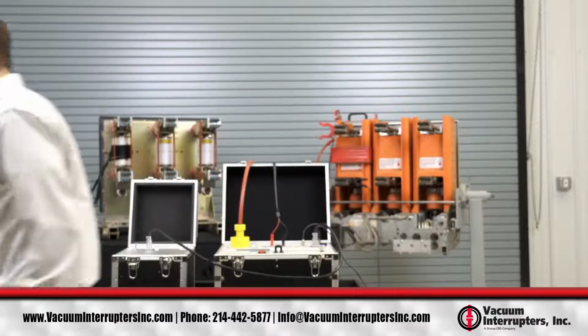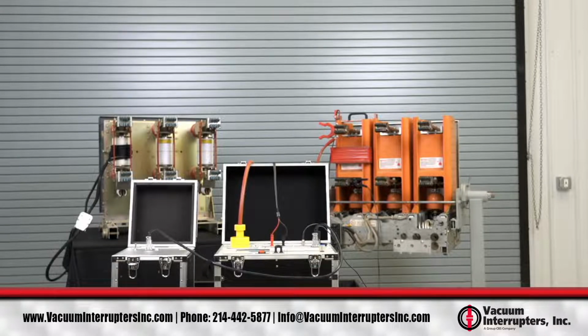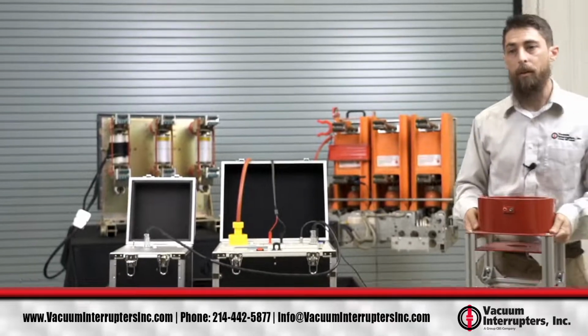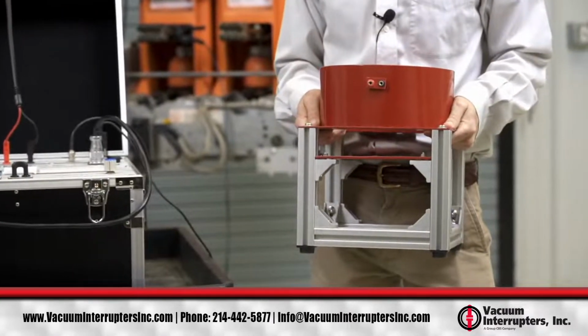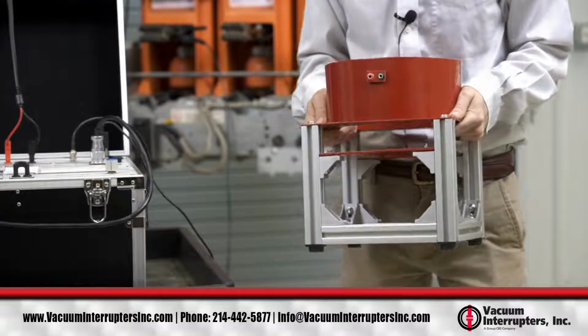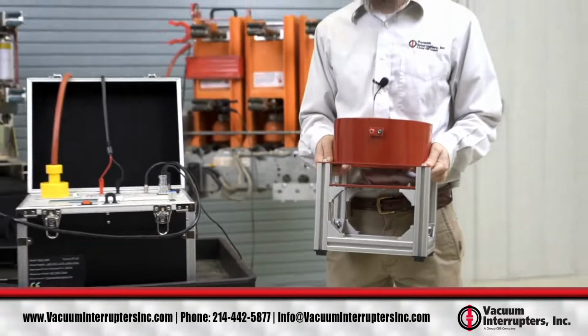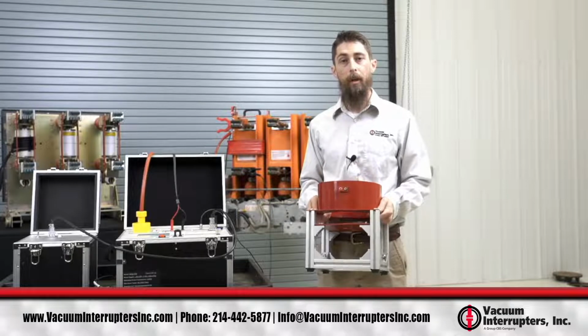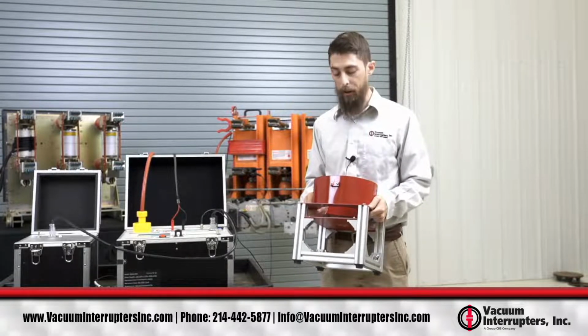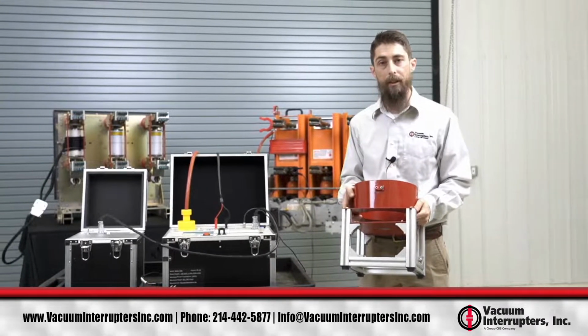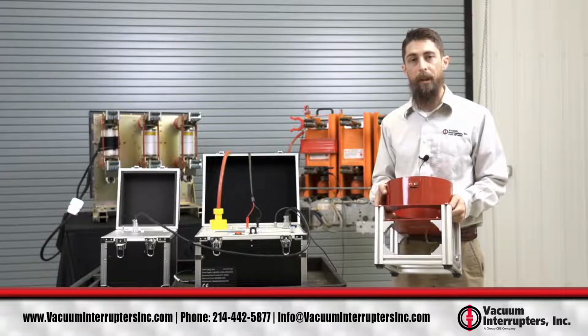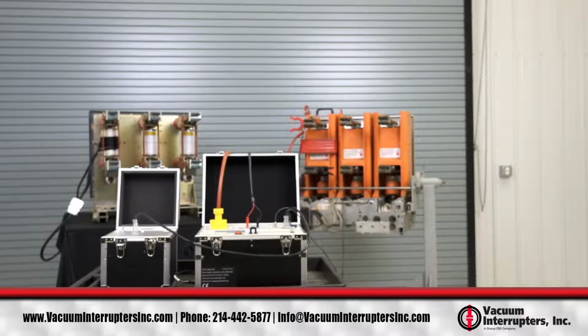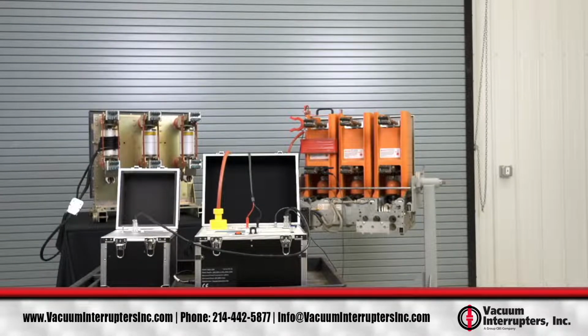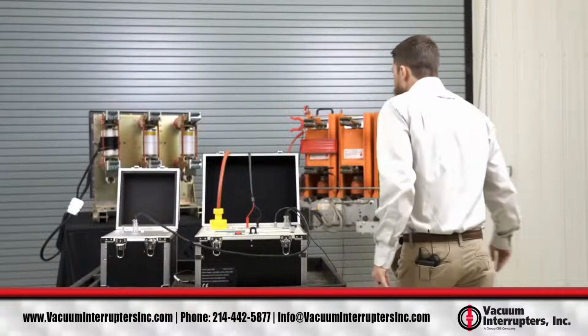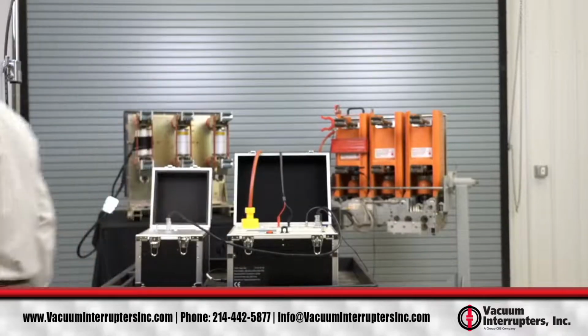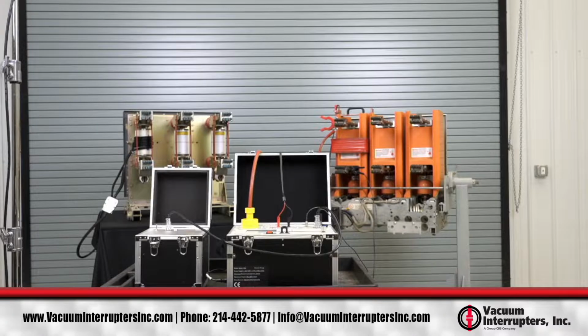We have our other coil options I can show you. So this would be our fixed coil. Most end users wouldn't have a need for a fixed coil because they test the vacuum interrupter while it's still installed in the circuit breaker. However, for service shops or OEMs that manufacture vacuum circuit breakers, this would be something that would make testing a lot easier for them. This is what we use in-house. We test every single vacuum interrupter that leaves our facility with the MAC test set.